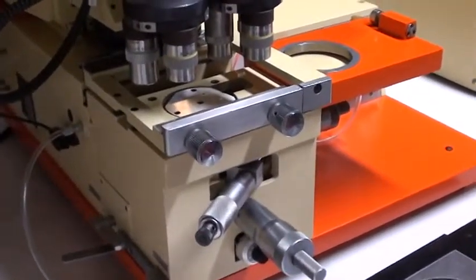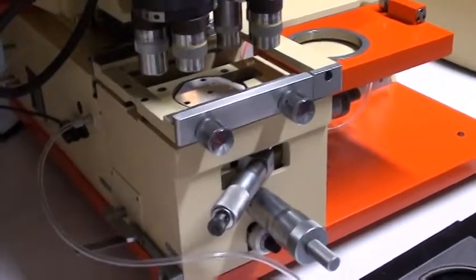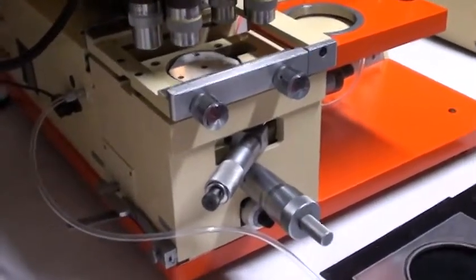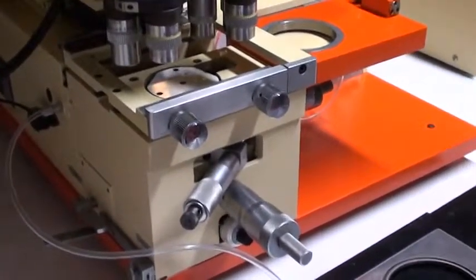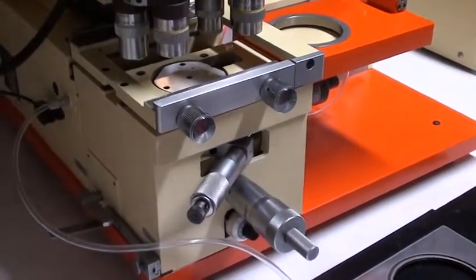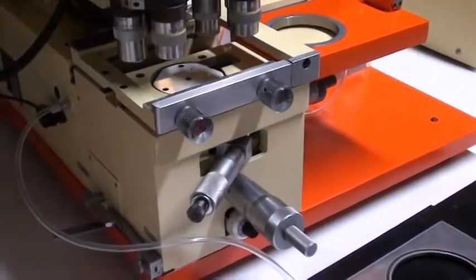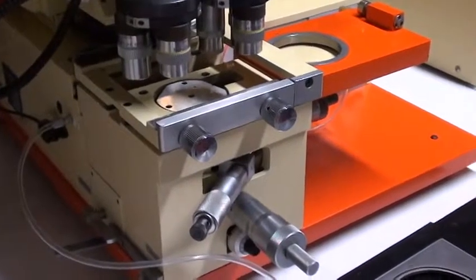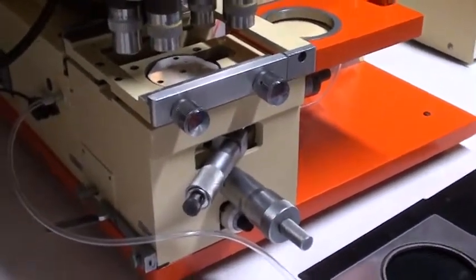The alignment stage has been completely refurbished with all new bearings, seals, and O-rings, tubing, fittings. The micrometers have been rebuilt. A new height adjustment knob has been included. New bladder tubing and new internal tubing is also there.